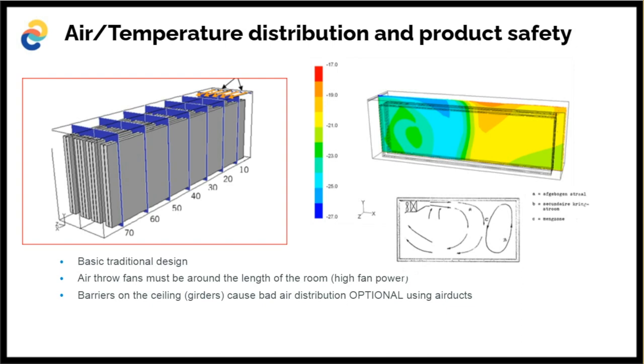it could work. But now they're going to get bigger and longer. Let's say the maximum air throw of a cooler is around 70 meters, 60 meters, depending on the cooler supplier. But when you go to 150 meters, you get this kind of effect. As you can see on the right bottom, you see these secondary flows going on in your cold store. And what's going to happen is nicely shown here in a CFD calculation: you're going to get quite a big temperature difference throughout the room. It's very nice to see that in a simulation.